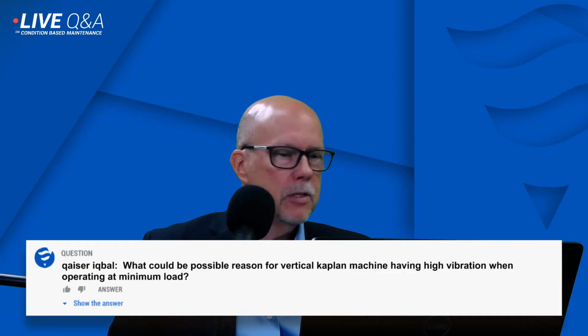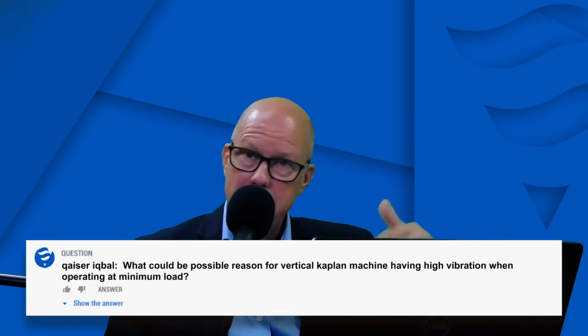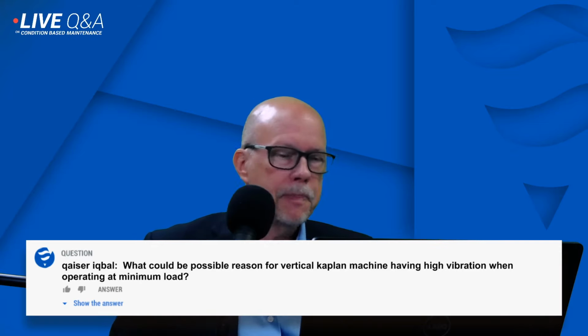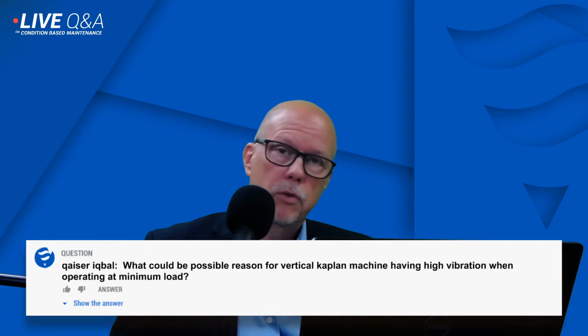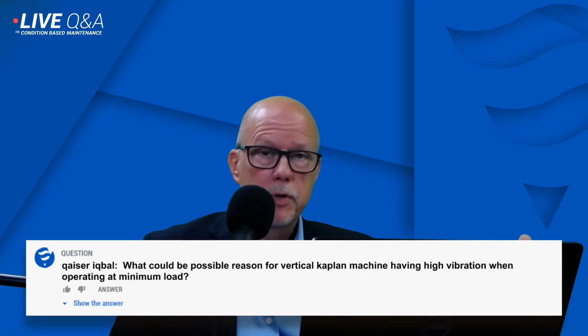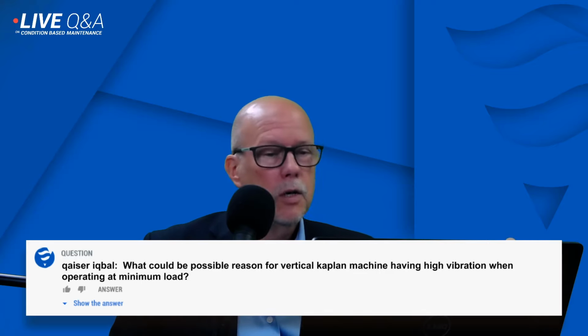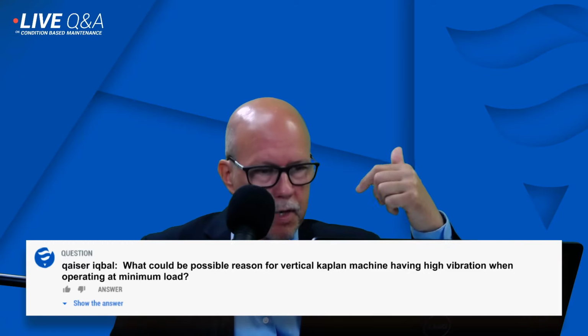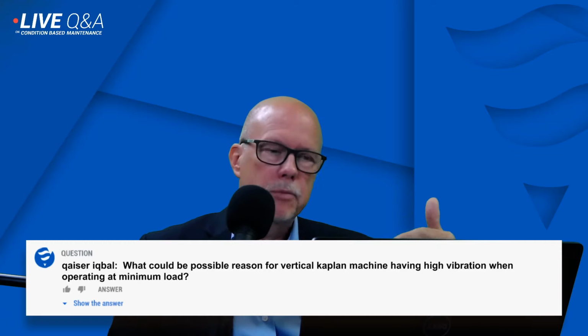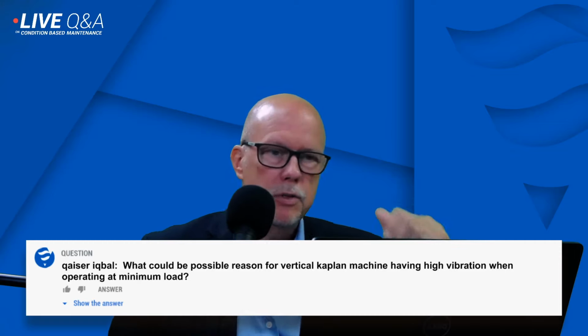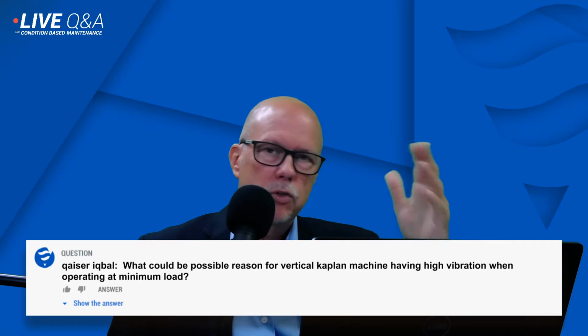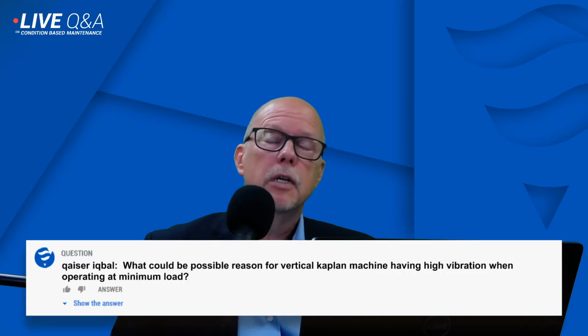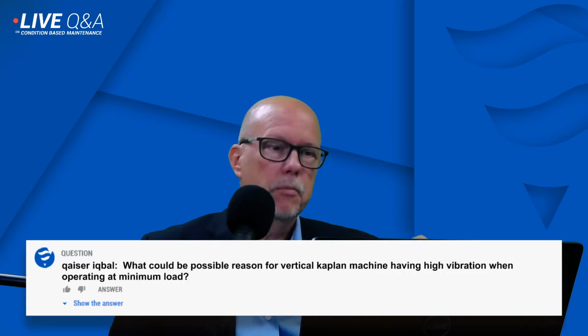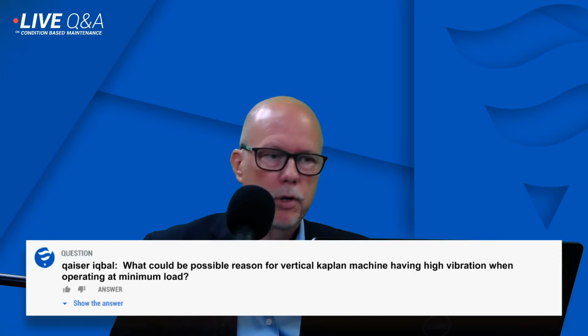We call it skating. So it becomes erratic and it starts wobbling around, but at a slower speed than the actual rotating speed. You also have, in some cases, the opposite. When you go into the rough zone, you will see some supersynchronous frequencies show up, supersynchronous harmonics, where the unit will actually spin on itself multiple times per rotation. So if let's say the fundamental is 3 hertz, you might see a 9 hertz or a 12 hertz frequency show up, which is predominant. So the unit is actually spinning on itself multiple times per rotation. We see that on some occasions, and those are all phenomena that can occur in the rough zone.